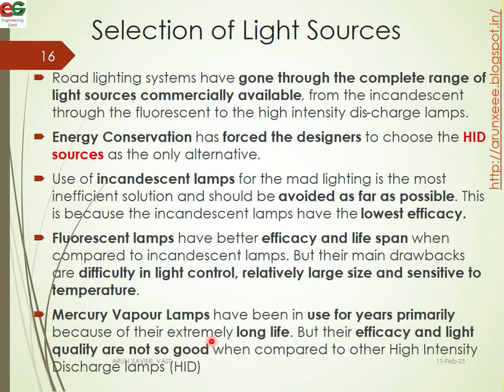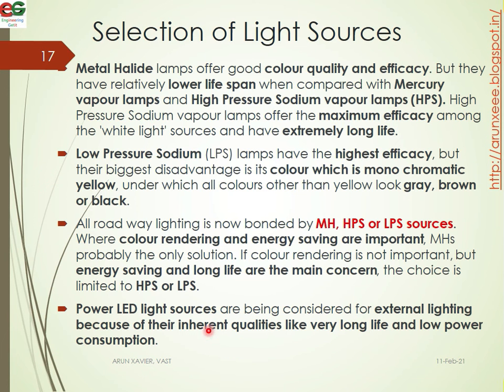Metal Halide offers good color quality and efficiency. Metal Halide lamps are better compared to Mercury lamps, but they have a relatively lower lifespan. High Pressure Sodium Vapor lamps offer maximum efficiency among white light sources and have an extremely long life.